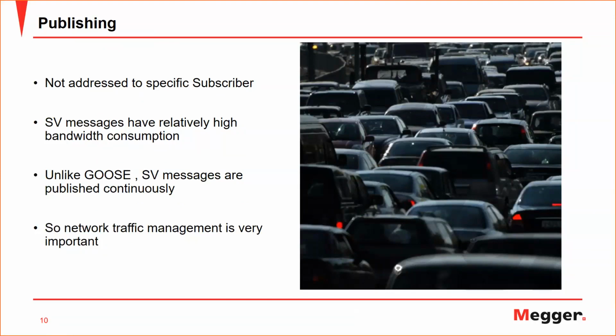And since these values are continuous, usually they will have a relatively high bandwidth consumption. If anyone is familiar with the GOOSE messages that are defined by the IEC 61850, they are not like the SV messages. They are published messages, but they are not like the SV streams, since the streams are continuous. And this network traffic management is very important when you are talking about sampled value. Your network should be able to withstand this stream and all the other traffic available to it. Just to give you an example on this, if I have a sampling rate of 4800 for the 60 hertz per second, the bandwidth of that stream will be approximately 5.6 megabit per second.